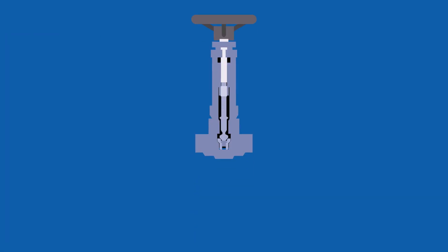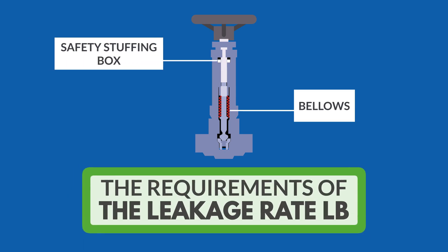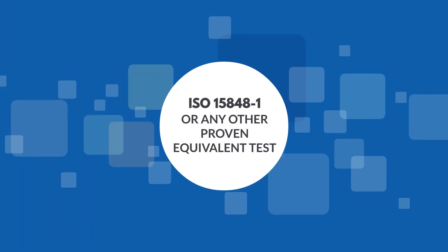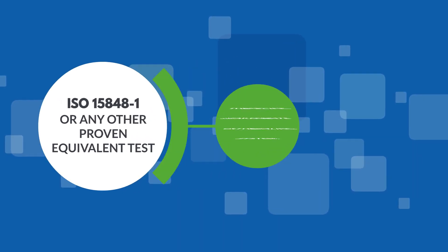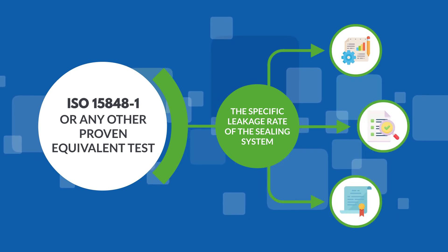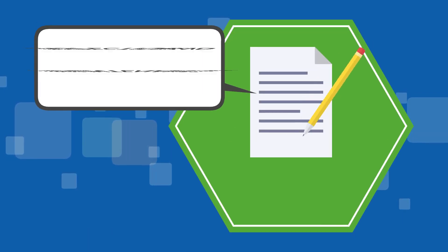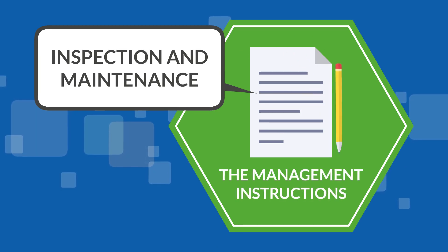Also, seals of spindle bushings, designed as high-quality sealed metallic bellows with downstream safety stuffing boxes shall meet the requirements of the leakage rate LB without individual verifications. Otherwise, ISO 15848-1 or any other proven equivalent test must verify the specific leakage rate of the sealing system for testing, evaluation, and qualification. The inspection and maintenance requirements of the sealing systems must be specified in the management instructions.